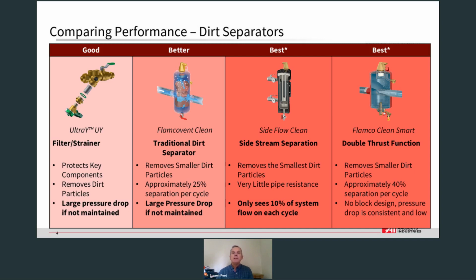So to help with the maintenance issue, the latest air and dirt separators on the market do not have brushes, blades, or other obstructions that slow the water flow. Instead, a double thrust function is used, and in that process, the first thrust effect is created by a separation chamber that separates the contaminated water. The second effect is created by returning that clean water back to the main flow again via an injection point, which pushes the bubbles and the dirt particles in the water to the outside of the chamber where they're separated again.